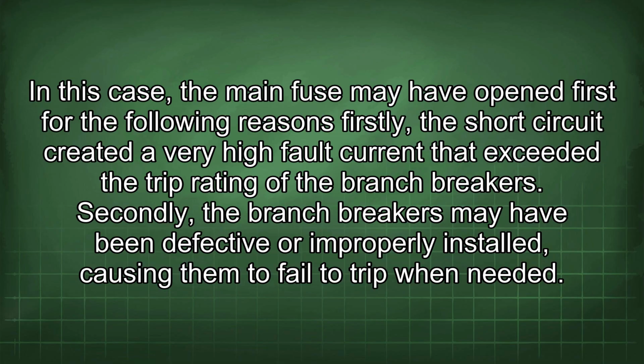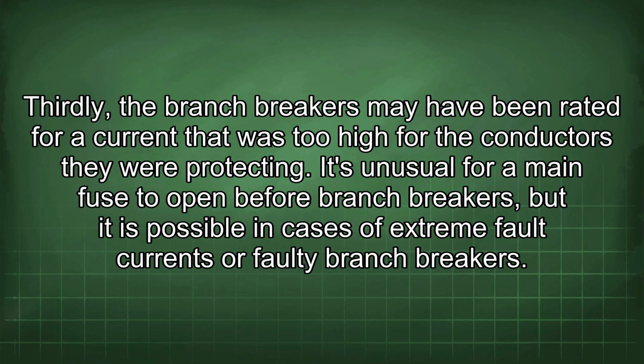Firstly, the short circuit created a very high fault current that exceeded the trip rating of the branch breakers. Secondly, the branch breakers may have been defective or improperly installed, causing them to fail to trip when needed. Thirdly, the branch breakers may have been rated for a current that was too high for the conductors they were protecting. It's unusual for a main fuse to open before branch breakers, but it is possible in cases of extreme fault currents or faulty branch breakers.